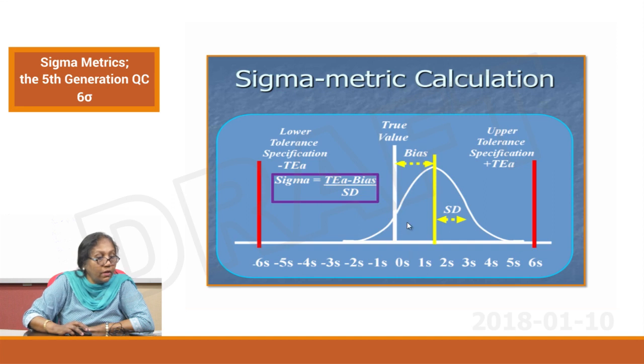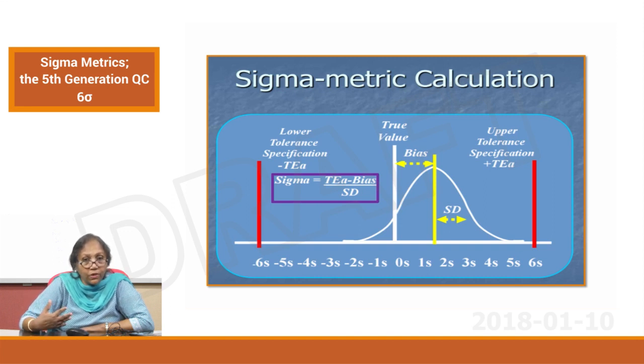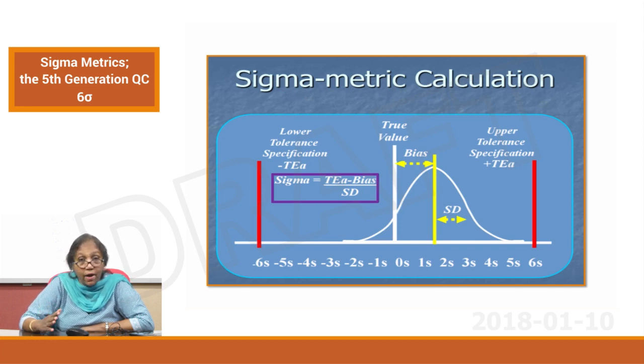Look at this graph — there is a certain amount of bias built up. This is one standard deviation, two standard deviations — it has already taken up four standard deviations, and the graph can only shift maybe one more time before it comes to the upper end of the allowable limit. This is called critical systematic error — how much can your mean shift? That is a very important question, so that you know you have to hold your mean in a certain position, avoid biases, and correct systematic error.